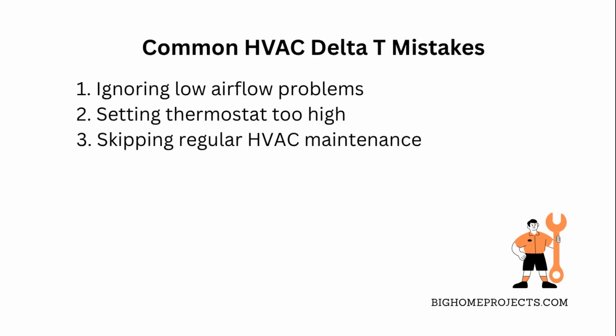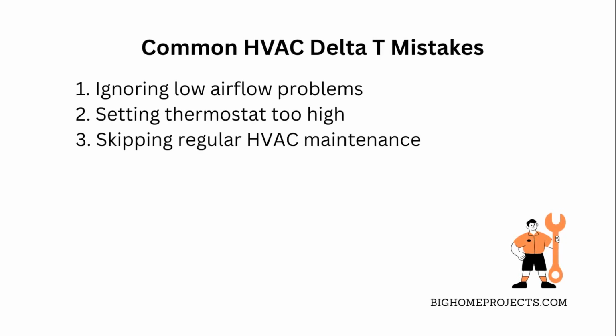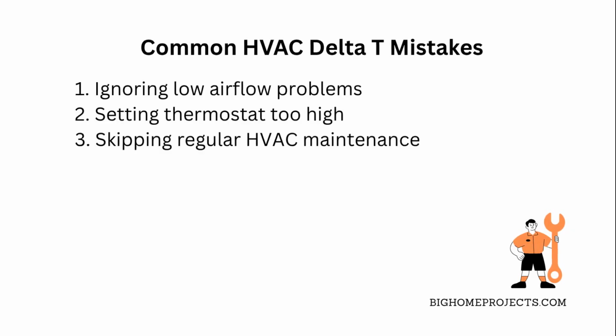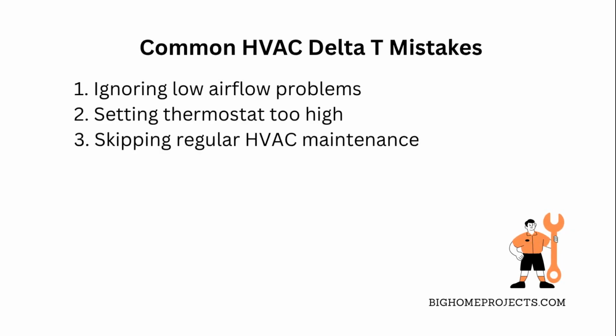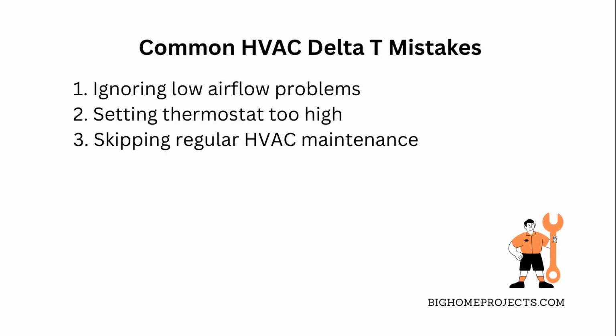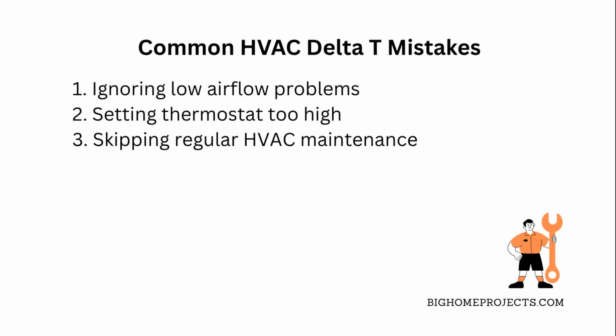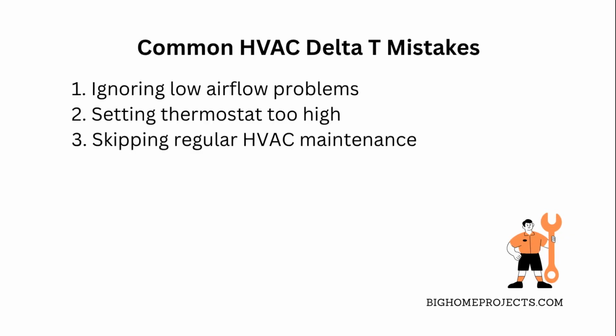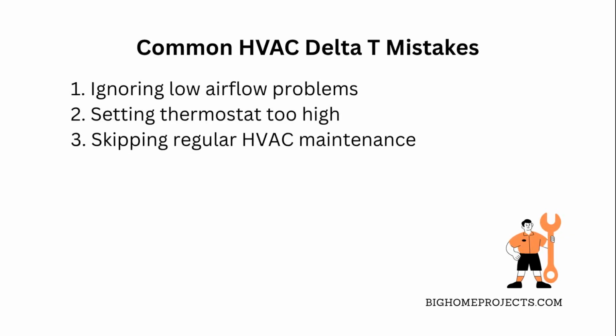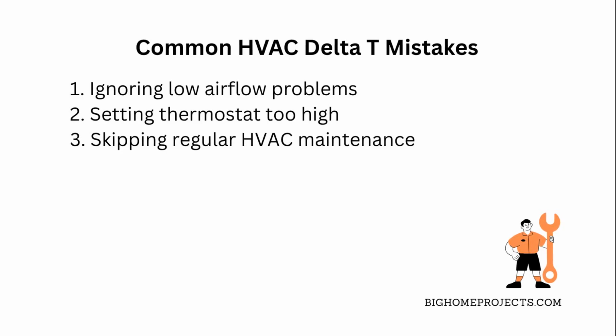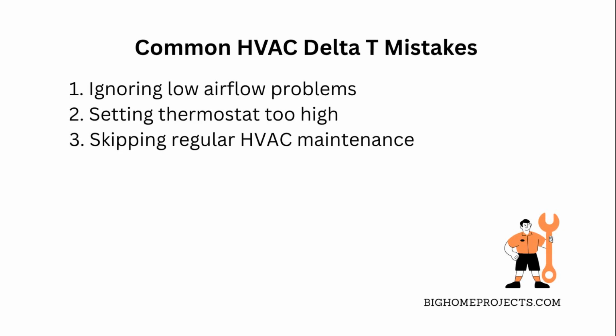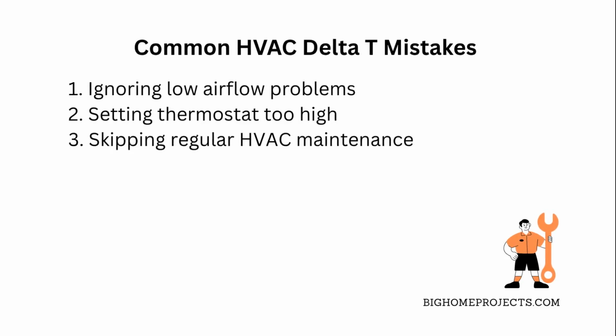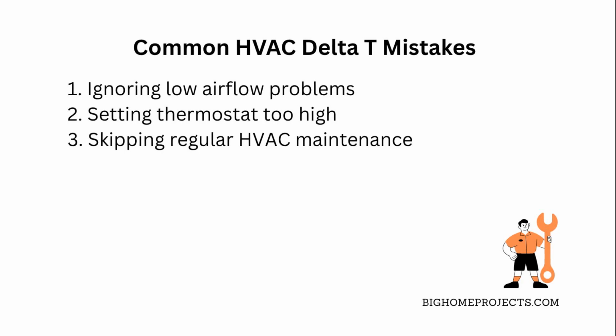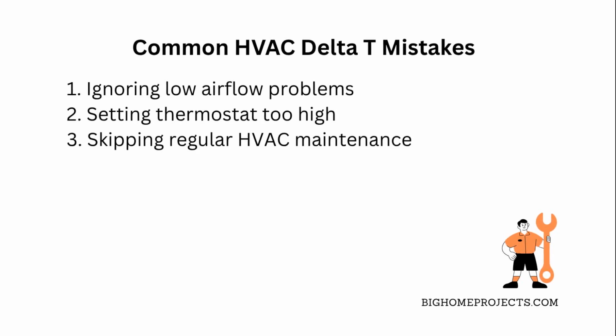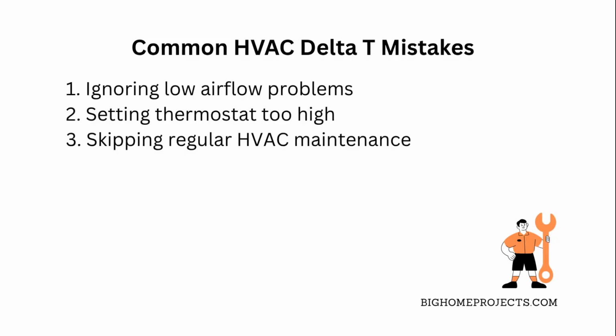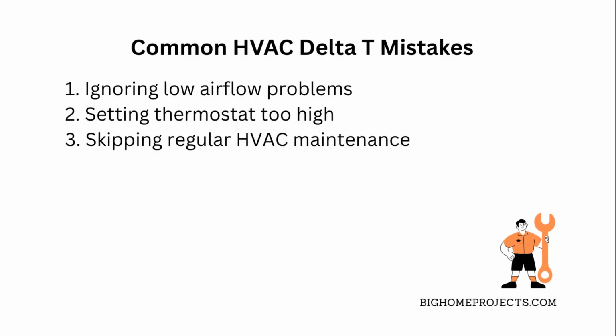One of the biggest mistakes with HVAC Delta T during electric strip heating is ignoring airflow problems. Too low airflow causes Delta T to spike, so always check and clean filters and ducts. Another common issue is overheating due to thermostat settings being too high, which can cause the system to shut down or cycle on and off too much. Fix this by setting a moderate temperature and avoiding sudden changes. Third, people often skip regular HVAC maintenance, leading to unnoticed malfunctions like blower motor issues or faulty sensors. Getting professional tune-ups helps prevent those headaches and keeps Delta T steady.